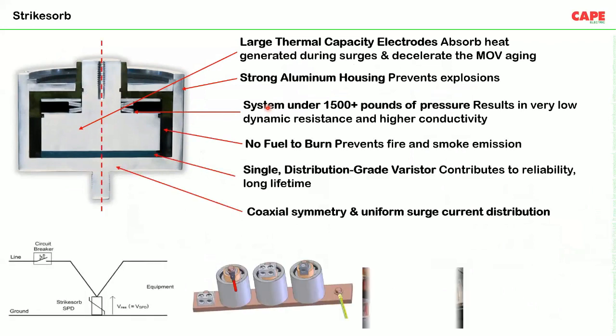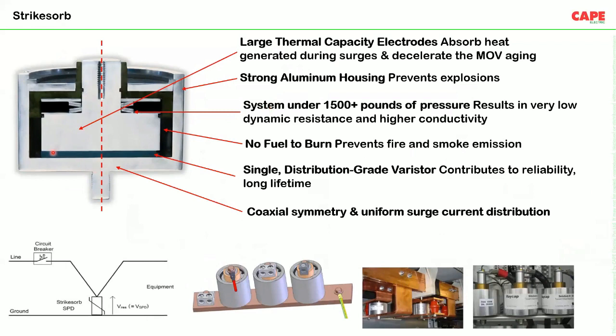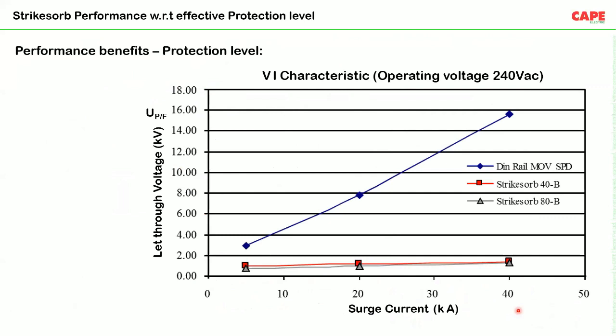Now, for example, StrikeSorb. This is actually a very special SPD, which has, you can see here, a large thermal capacity electrode to absorb the heat. It has a metal oxide varistor, and the construction looks something like this. The SPD can be mounted on the bus bar. The advantage of this SPD is, next seminar, we will see the disadvantage with the connecting wire length. The advantage of StrikeSorb is that, since we are eliminating the connecting wire, the ultimate protection level of this SPD is much better than a DIN rail mounted SPD.